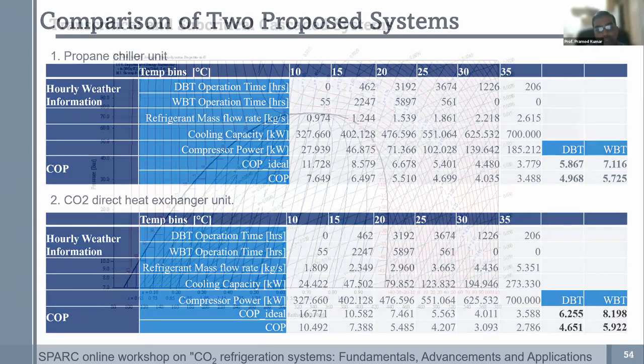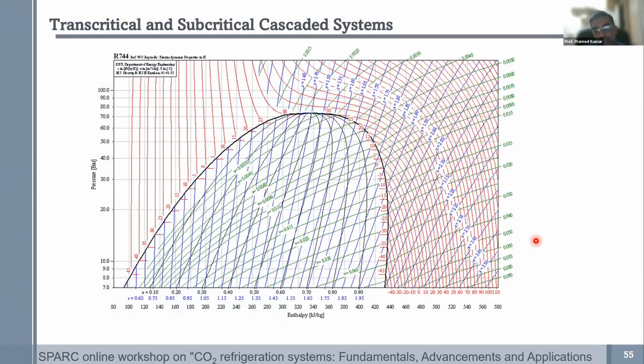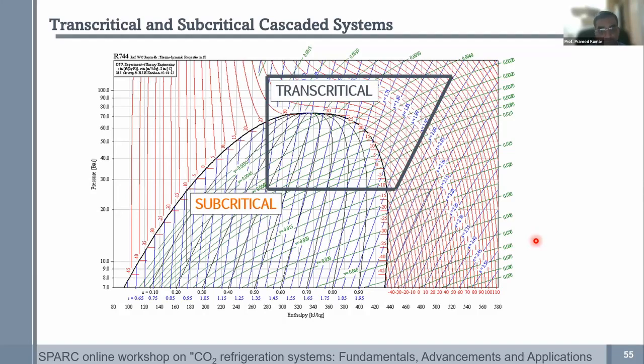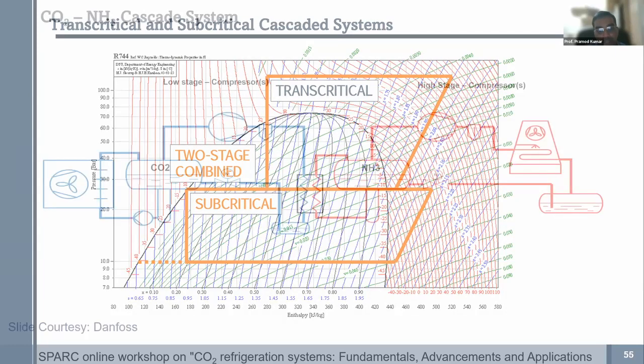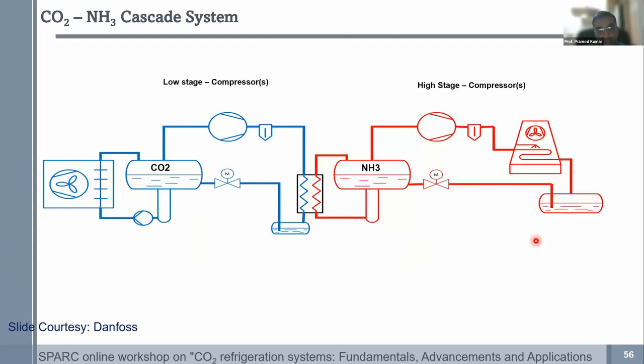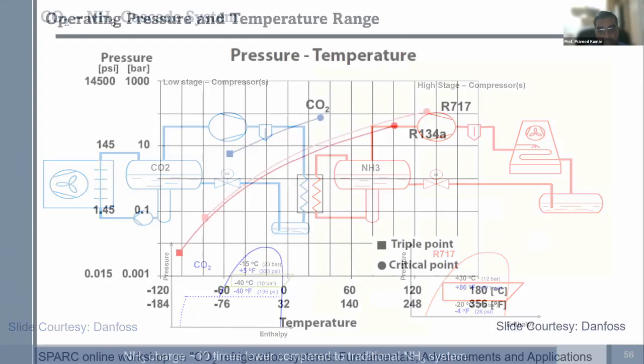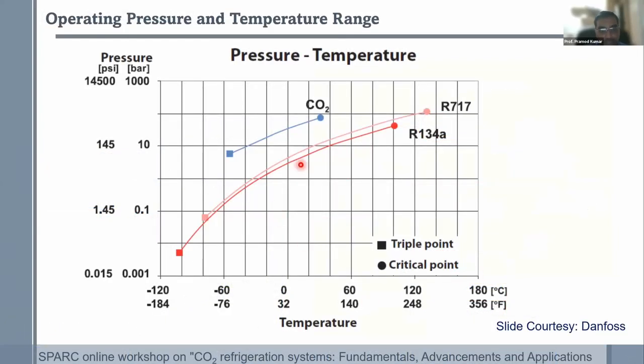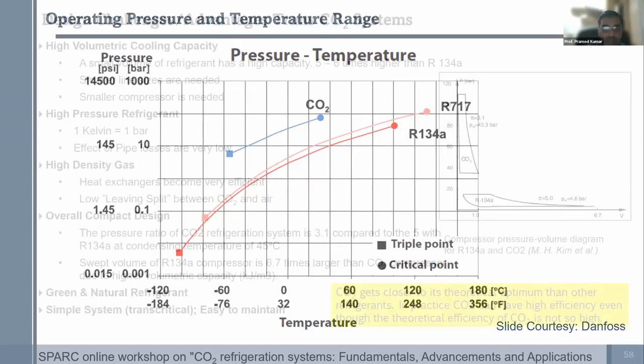Another important thing is that you can now combine transcritical and subcritical systems to produce cascade systems. I'm not going to go into the details of it. One gaining popularity worldwide is a two-stage system with carbon dioxide as the circulating medium instead of brine, and the high stage system with ammonia. So this is gaining popularity worldwide. What it tells you is that with a carbon dioxide system, you can still go to close to about minus 55 degrees Celsius and still operate above atmospheric pressure. That offers a great deal of simplicity, as you will not be operating under vacuum, where air can potentially get into the system.